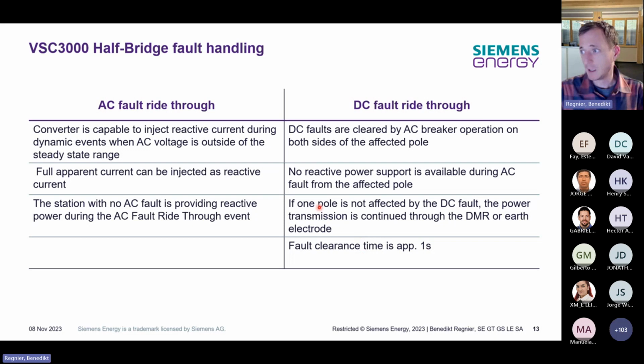And if the event is on one pole, the other pole can still operate, especially in the bipole configuration. So there are a lot of possibilities. Also here, for dynamic performance, it's very important to talk with the customer to get the boundary conditions from the customer and then decide in which way we can optimize the control and protection system to make it as adapted as possible for this situation.